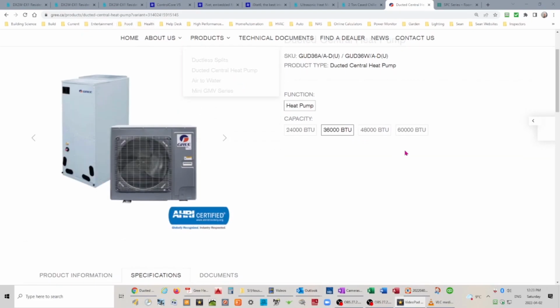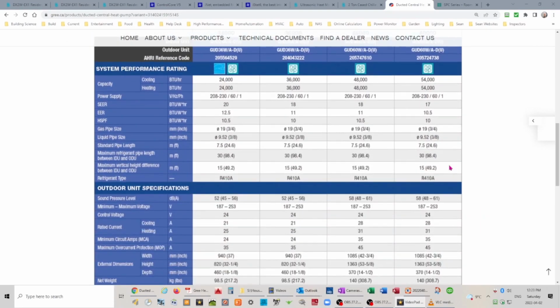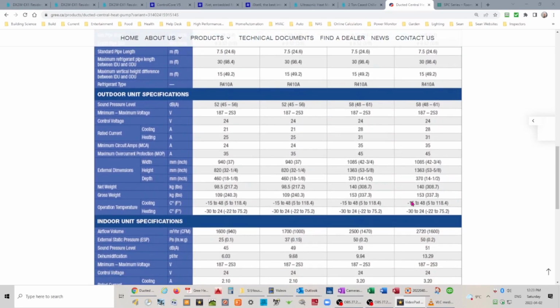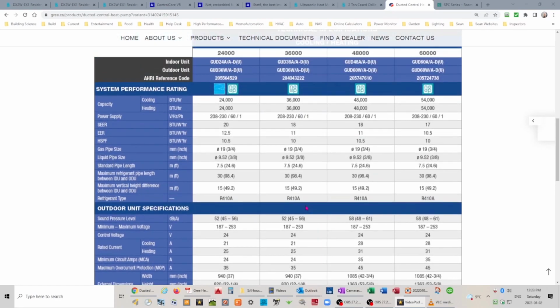The GREE heat pump has an operational range of -30 to 24 Celsius in heating mode and -15 to 48 Celsius in cooling mode, and an advertised heating HSPF rating of 10 to 10.5 and a cooling SEER rating of 18 to 20. As this is the first mating of these two units, there is no overall performance ratings at this time, and we'll be trying to determine these over the next 12 to 24 months.